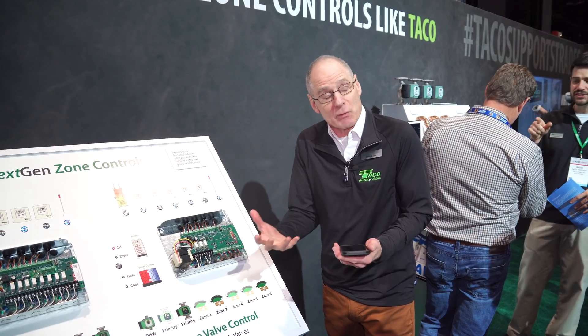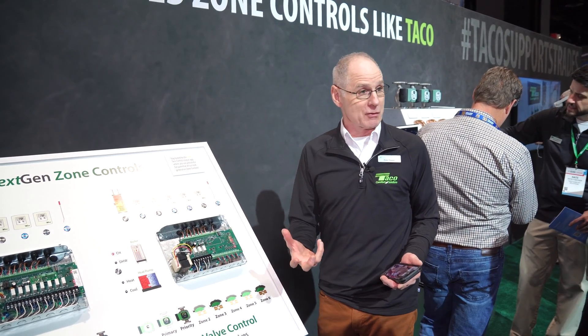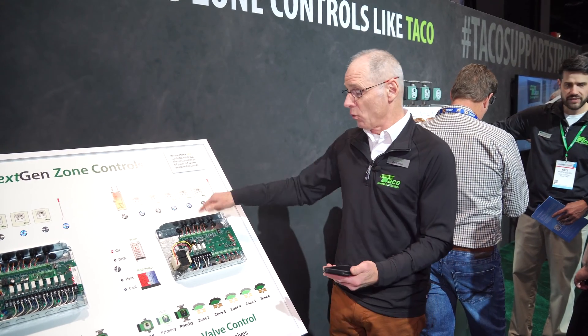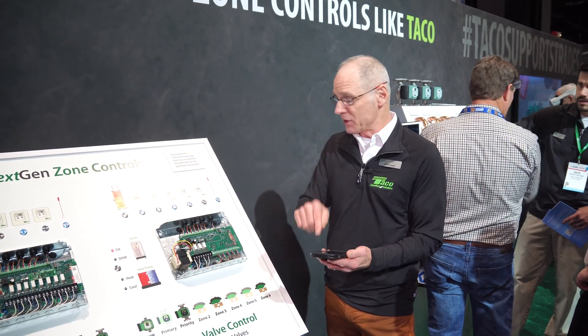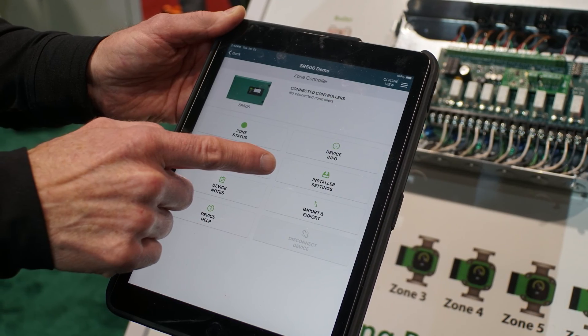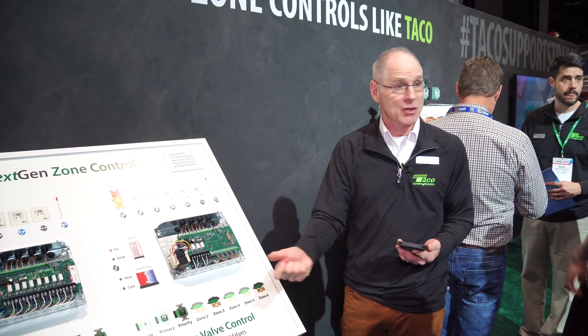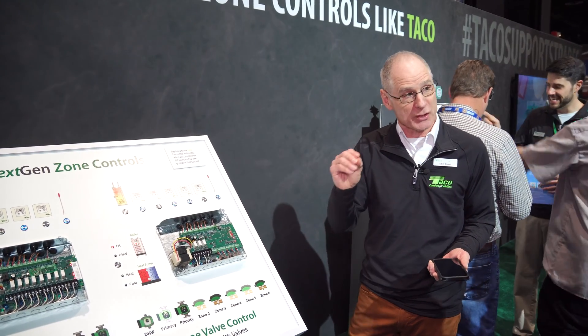But there are times when you may want to do something different. The perfect example is maybe zone 3 is a micro zone — very small. When it calls, the boiler runs 20 or 30 seconds and shuts off. It's annoying and not good for the equipment. So I can download our Taco Control mobile app, go in, find the main boiler end switch, and uncheck zone 3 so it will not enable that output. When zone 3 calls by itself, the heat already in the system or another zone turning on will satisfy it — we never short cycle it.